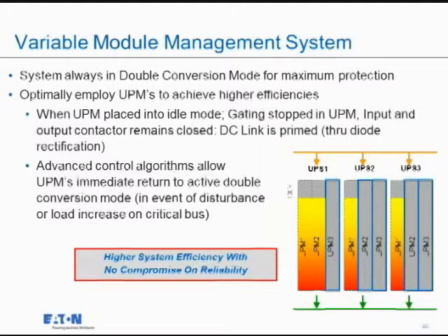Also, in doing so, I don't need to worry about my increments. Remember we talked a little bit about the incremental? When do I choose the blocks and the different size blocks? This gives me a lot more versatility, in that I can now step in smaller increments by simply engaging 2 modules on the first system. So the discreteness of my steps allows me further to optimize for the given loads.